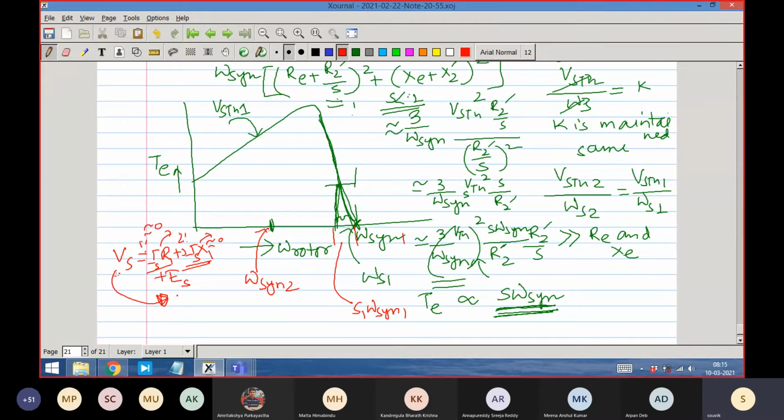So effectively 95, 96, 97% of the supply voltage Vs is balanced by Es. The essential thing that is happening in the machine is, when you supply the voltage at the terminal, you say what you expect the Es level to be. It will be slightly different due to current, maybe 1-2% different, but that is not the essence. The essence is that the supply voltage becomes almost equal to the induced voltage.